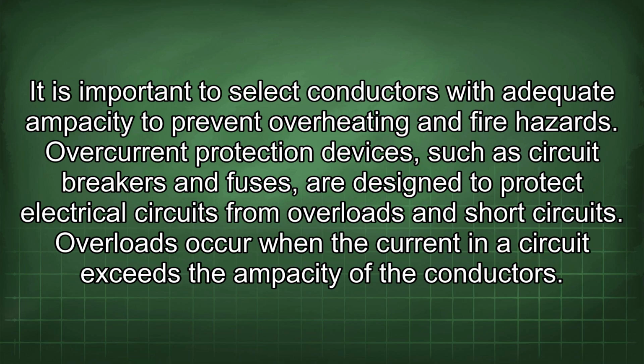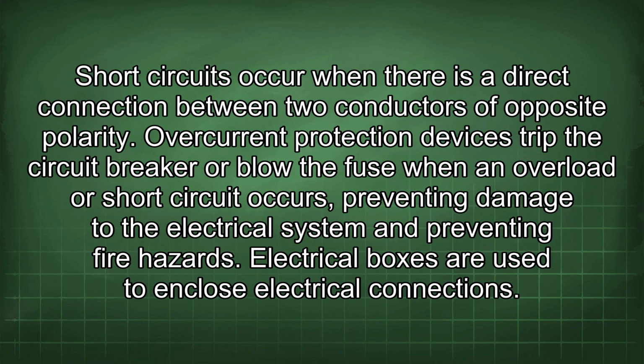Overcurrent protection devices, such as circuit breakers and fuses, are designed to protect electrical circuits from overloads and short circuits. Overloads occur when the current in a circuit exceeds the ampacity of the conductors. Short circuits occur when there is a direct connection between two conductors of opposite polarity. Overcurrent protection devices trip the circuit breaker or blow the fuse when an overload or short circuit occurs, preventing damage to the electrical system and preventing fire hazards.